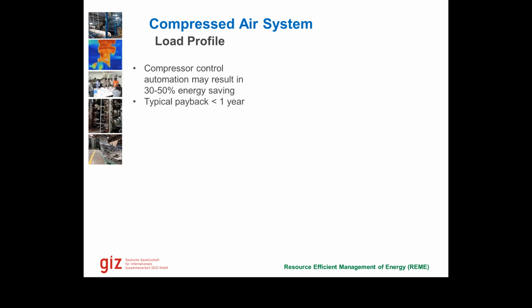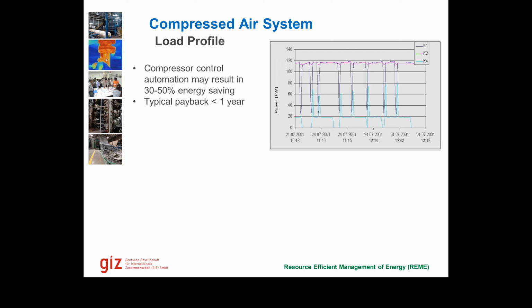Then talking about load profile, if we automate the compressors, if we have multi-compressor systems, these may result in 30 to 50% energy savings typically, because multi-compressor systems are not controlled very well only by pressure modulation, but we need to have an intelligent control system there with VFDs as well.